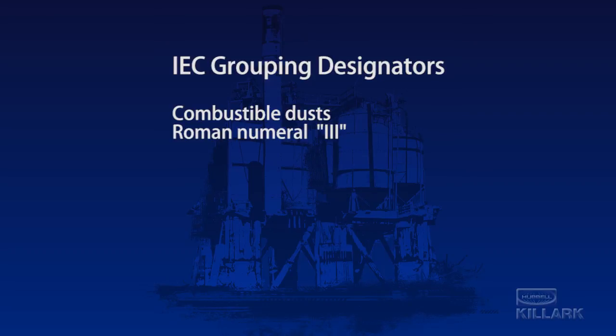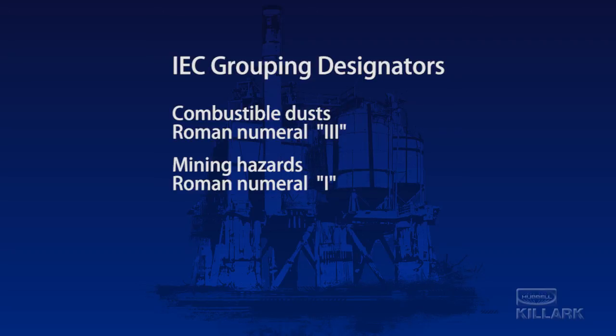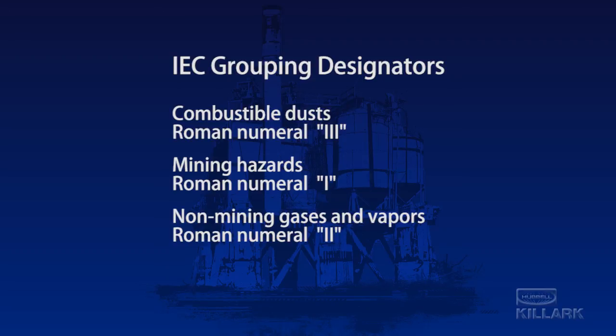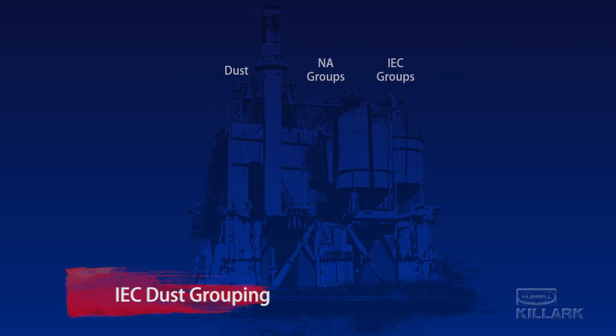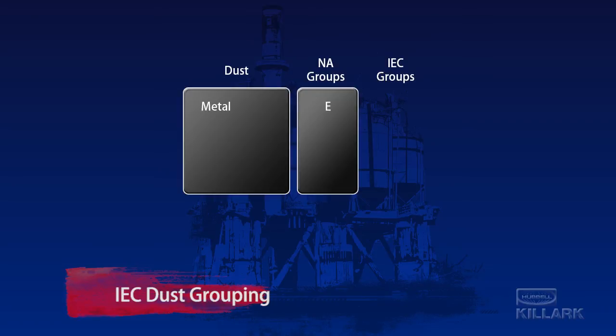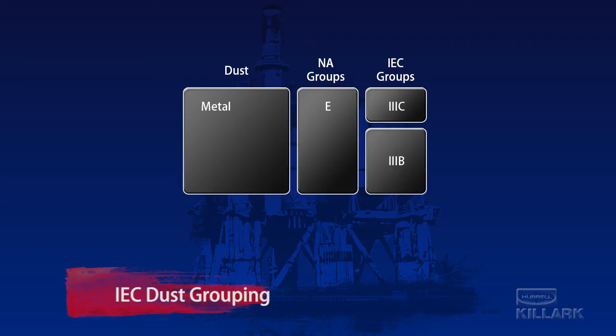The groups assigned for dusts are preceded with the Roman numeral 3. Remember, this is part of the series where Roman numeral 1 identifies explosive byproducts found during mining, and Roman numeral 2 designates non-mining gases, vapors, and flammable liquids. Again, in seemingly reverse order from the division system, Group 3C includes conductive dusts. Group 3B covers non-conductive dusts and combines Groups F and G from the division system.